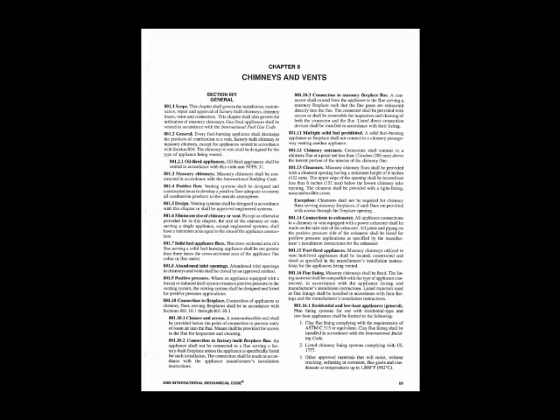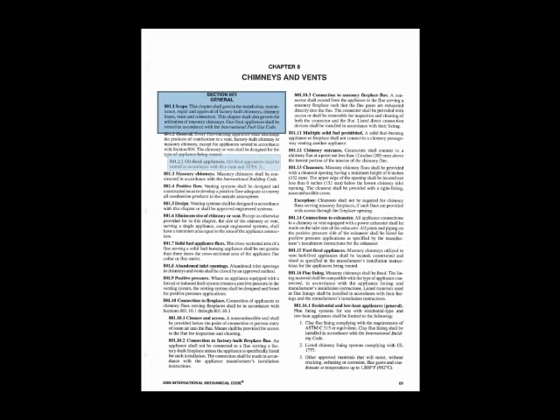Chapter 8 is chimneys and vents. We start off with the scope. 801.1 says this chapter shall govern the installation, maintenance, repair of factory-built chimneys, chimney liners, and vent connections. It does refer to the fuel gas code for gas-fired appliances. Oil-fired appliances, it also talks about in 801.2.1, refers to NFPA 31. It gives you ideas of masonry chimneys, positive flues, design of systems. Solid fuel appliances, it talks about abandoned inlet openings, and they have to be closed. It talks about positive pressure. Most chimneys will work on a negative pressure, a vacuum. In this section, Section 801 actually serves as some good definitions for the entire chapter.